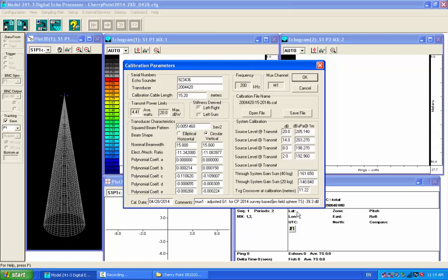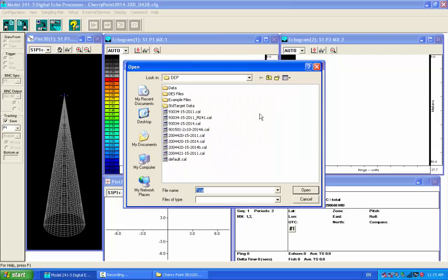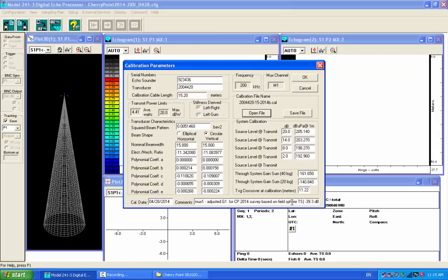And then we did come back and do a post survey laboratory cal, and it did spec right in with. You're doing good in the field. I done good, so I was happy about that. But anyway, for the most part, what you're going to do here is, we can set these up for you too and update your configuration files. But if you had a 2014 cal and we didn't have the computer or hadn't set it up for you, and just sent you the cal file, here's where you just pick it up and attach it, and then it would just update.